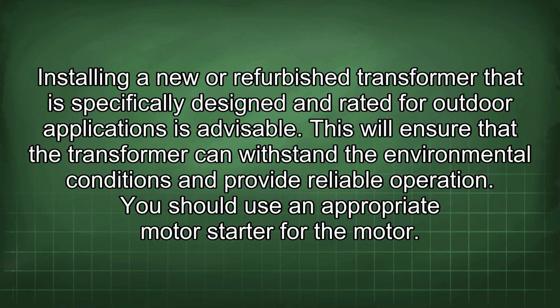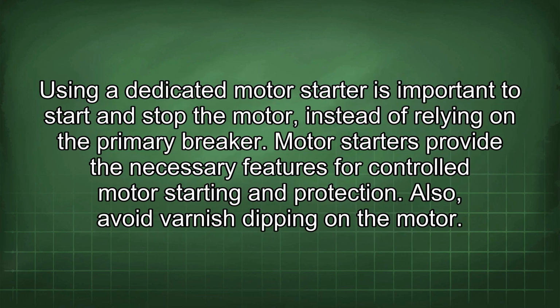Installing a new or refurbished transformer that is specifically designed and rated for outdoor applications is advisable. This will ensure that the transformer can withstand the environmental conditions and provide reliable operation. You should use an appropriate motor starter for the motor. Using a dedicated motor starter is important to start and stop the motor instead of relying on the primary breaker. Motor starters provide the necessary features for controlled motor starting and protection.